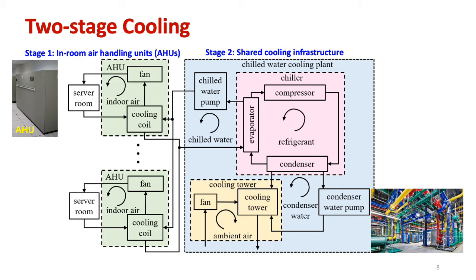We consider a 2-stage cooling system. The first stage consists of the in-room air handling units. The second stage is the shared cooling infrastructure supporting the whole data center. We model the inter-room heat transfer to be a linear function of the difference between the 2 rooms' temperatures. The coefficient alpha depends on the area and the material of the separation between the two rooms.